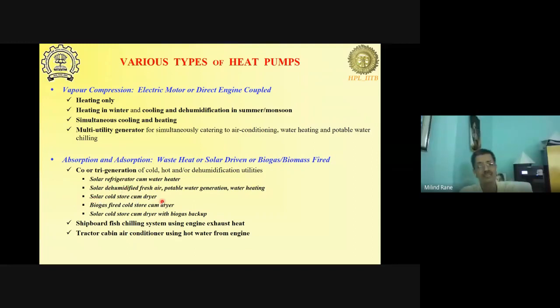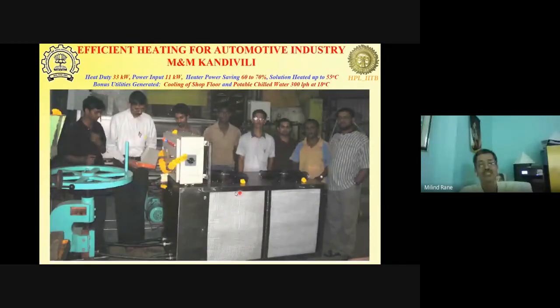We have done this. They can be backed up with solar PV or solar thermal, and biomass backup can be there for the cold stores and all, in case the sun is not available. Shipboard chilling using engine exhaust from the fishing trawler engine exhaust. We have done this, and currently also we have one project going on. This morning, just before this, I had a call from one of my clients who is installing this to produce potable water, desalinating seawater using this exhaust. Tractor cabin air conditioning. This was the first unit which we deployed in Mahindra & Mahindra, for 33 kilowatt of heating with only 11 kilowatt of input power, and air conditioning and chilled water of 300 liters per hour at 18 degrees was a bonus.